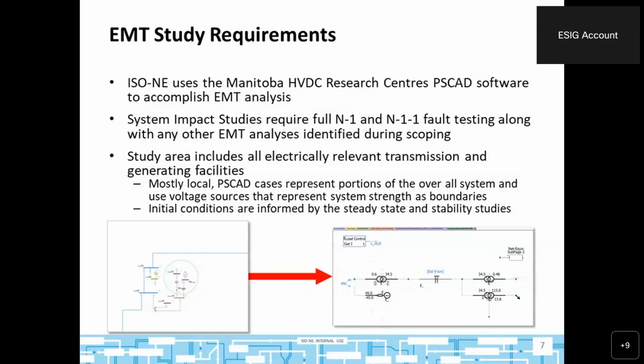When we run these cases, we start with initial conditions pulled from the original PSSE stability cases—initial power outputs, bus voltages, and angles all come from the PSSE cases. Using ETRAN to convert cases this way saves a lot of time in case building, since all the topology is directly ported over. This also lets us benchmark between PSSE and PSCAD to better understand what phenomena we may be missing in the stability studies, or vice versa in the EMT studies for the much larger Eastern Interconnection-wide system.